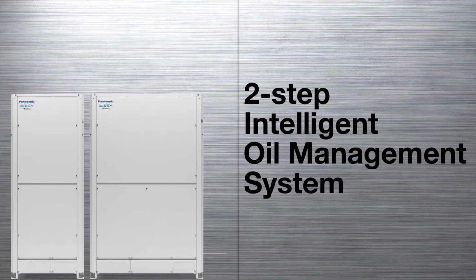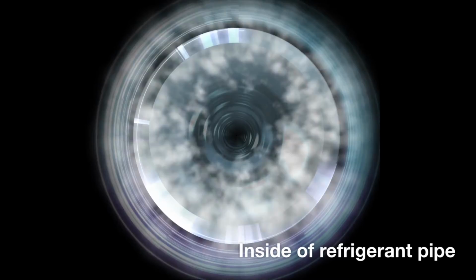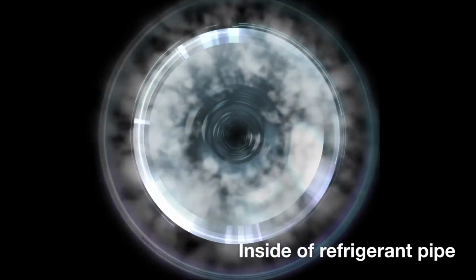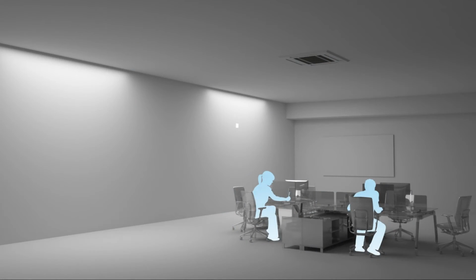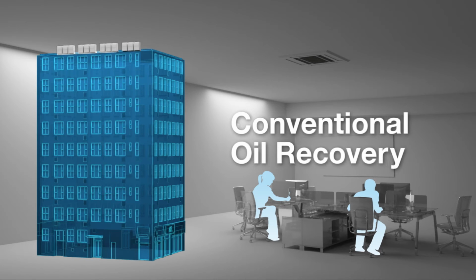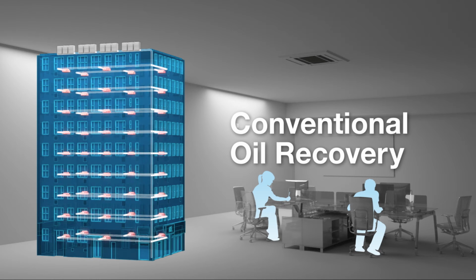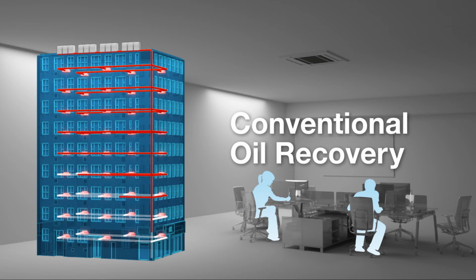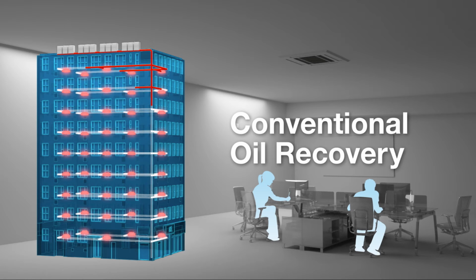Another key factor contributing to efficient operation is Panasonic's unique intelligent oil management system. The problem with oil recovery is that it generates unpleasant noise and vibrations in indoor units and forces units to unnecessarily operate with maximum output. In conventional systems that regularly practice oil recovery, this can lead to unnecessary use of electricity.